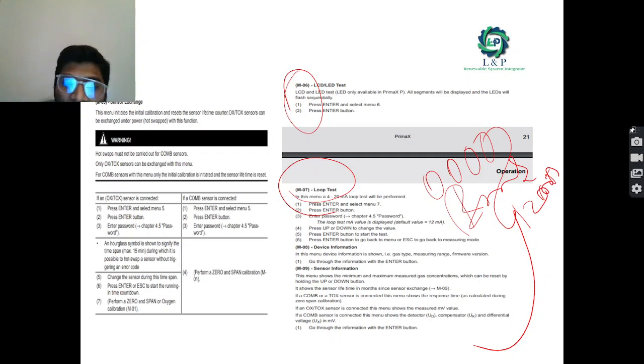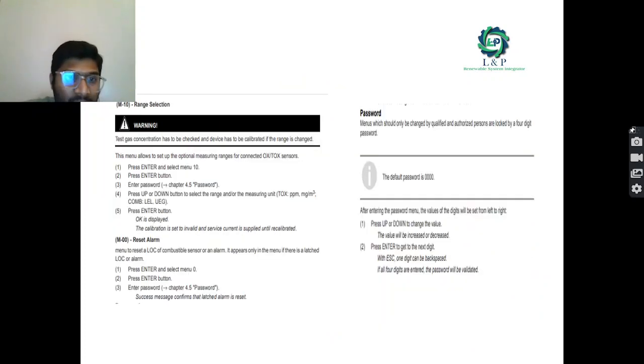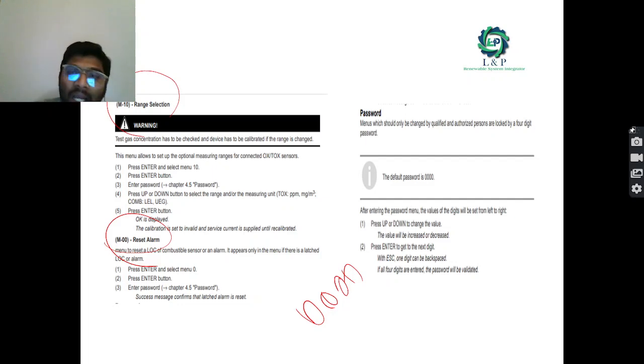Okay, if you want to see the device information, you can go into the menu 8, M08. If you want to get the sensor information, you can go inside the M09. Okay, and if you want to select the ranges, you can go into the M10. Okay, enter, go to the M10, press the enter button again and put the password. Okay, if you want to change the ranges, with the help of the upward and downward arrows, you can do it. Okay, if you want to do the reset, it is a basic one, M0. Okay, you can go into the menu to reset the combustible sensor alarms. Okay, it appears in the menu only if there is a latched LOC or alarm. Okay, and if you want to enter it, go to the M0, press the enter button and put the password. Okay, once it is done, a success message confirms the alarm is reset.